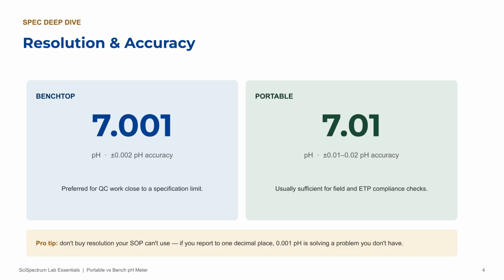Let's talk numbers. A benchtop resolves down to 0.001 pH, with accuracy around plus or minus 0.002. A portable resolves to 0.01 pH, with accuracy more like plus or minus 0.01 to 0.02. Now, if you're doing QC or stability testing close to a specification limit, that extra decimal place on the benchtop gives you real margin. But if you're doing a field or ETP spot check against a discharge limit, 0.01 is usually more than enough. And here's the pro tip I always give people. Don't buy resolution your SOP can't use. If you're only reporting to one decimal place, that 0.001 pH benchtop is solving a problem you don't actually have, and you're paying for it.